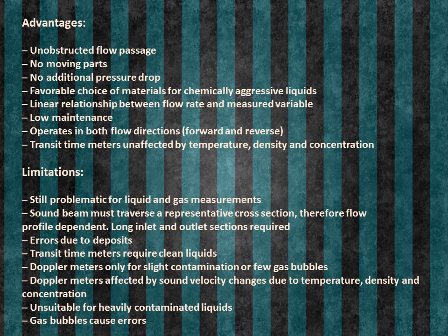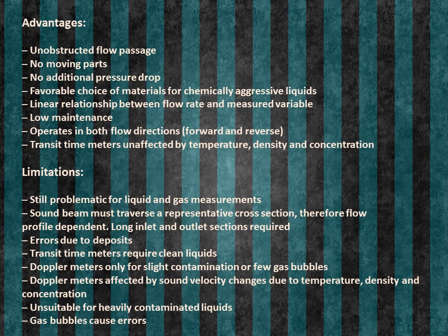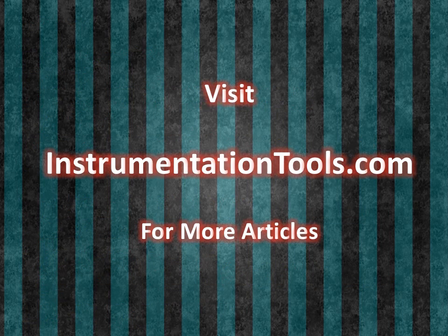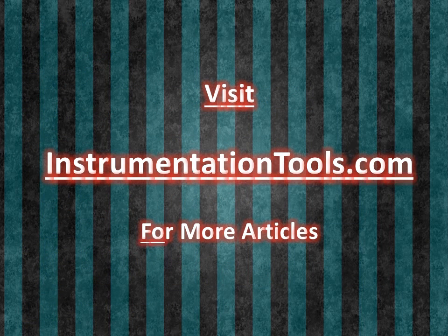Transit time meters require clean liquids. Doppler meters are only suitable for slight contamination or few gas bubbles. Doppler meters are affected by sound velocity changes due to temperature, density, and concentration. Unsuitable for heavily contaminated liquids. Gas bubbles cause errors.